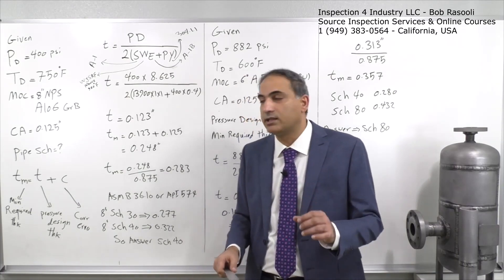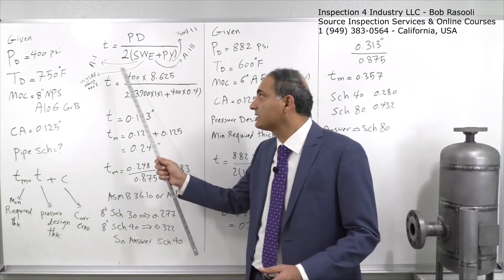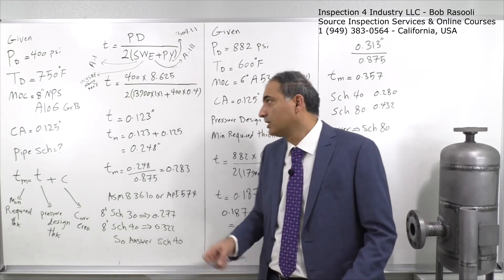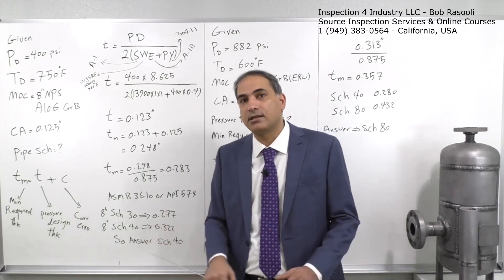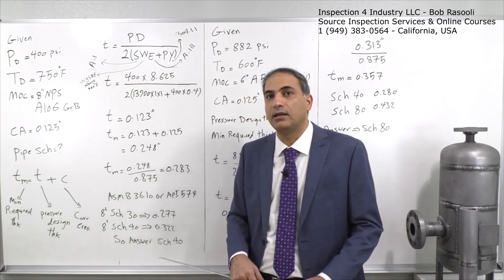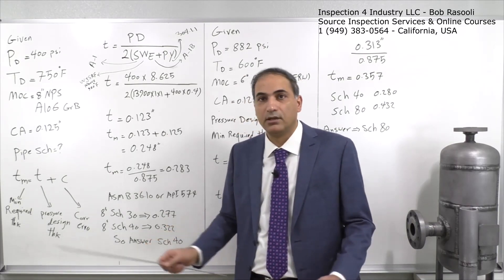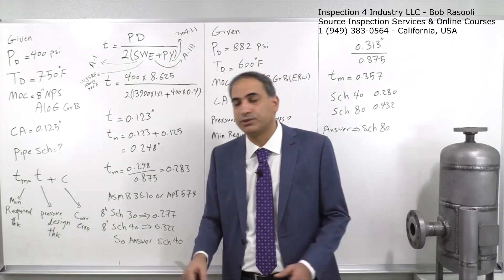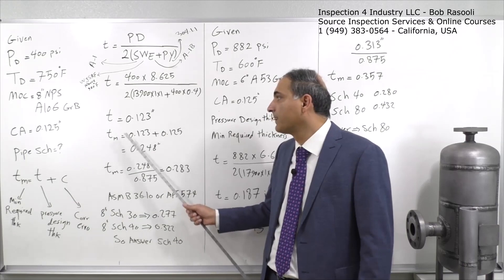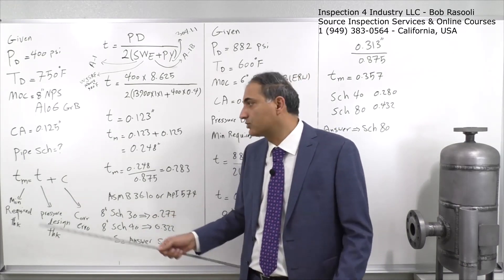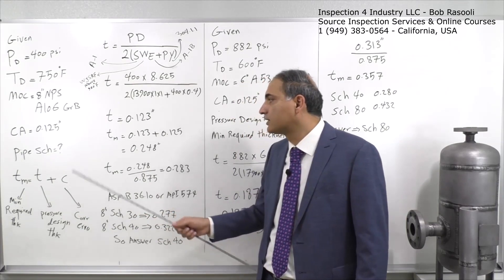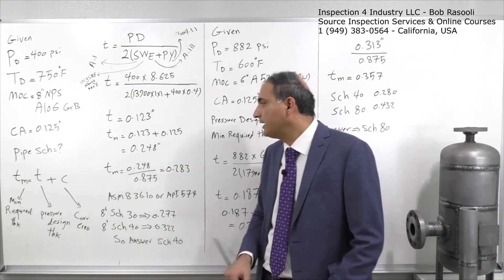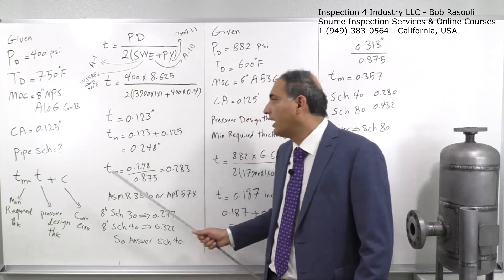This means we need 0.123 inches of wall thickness — with this material and allowable stress — to resist the internal pressure. If the problem only asked for the pressure design thickness, we would stop here. But since the problem asks for the pipe schedule, we must add the corrosion allowance. Adding 0.125 inches gives us 0.248 inches.